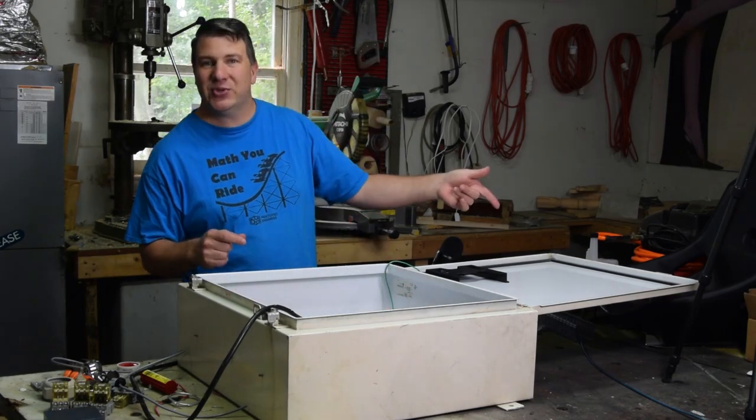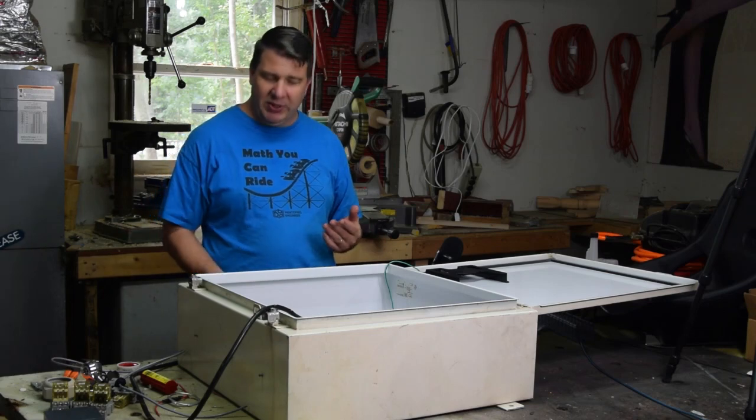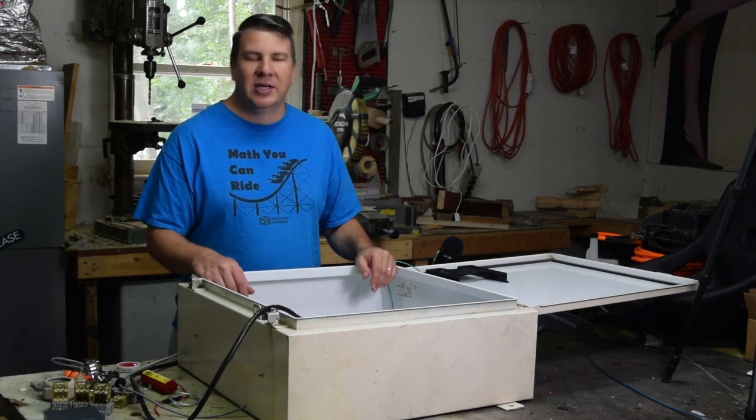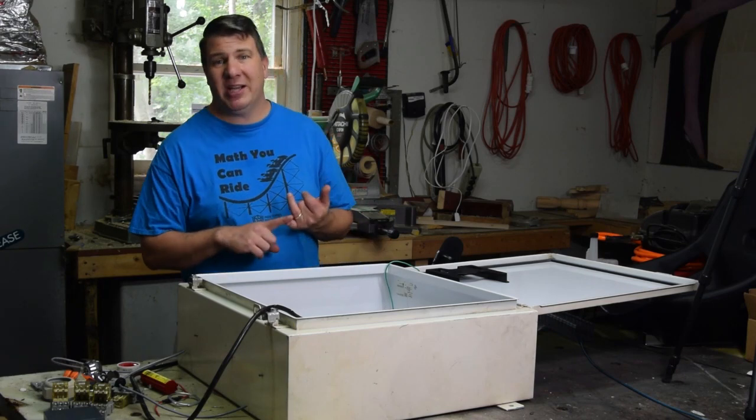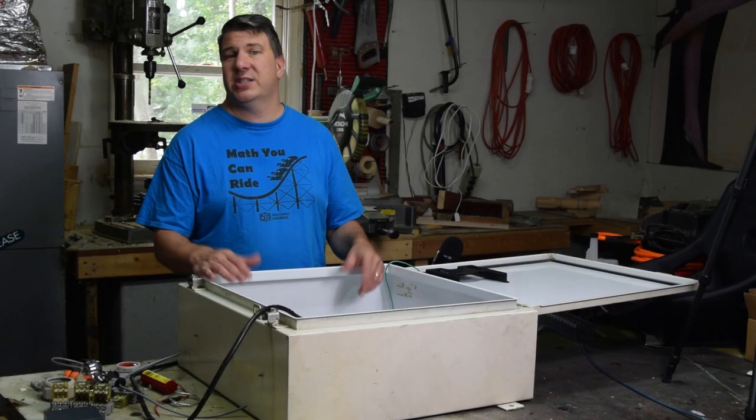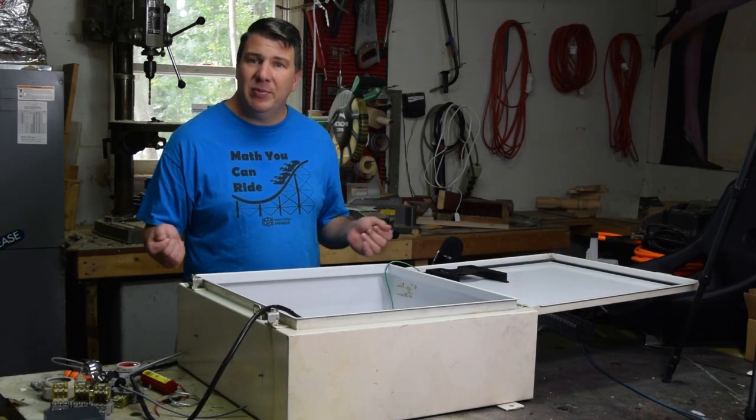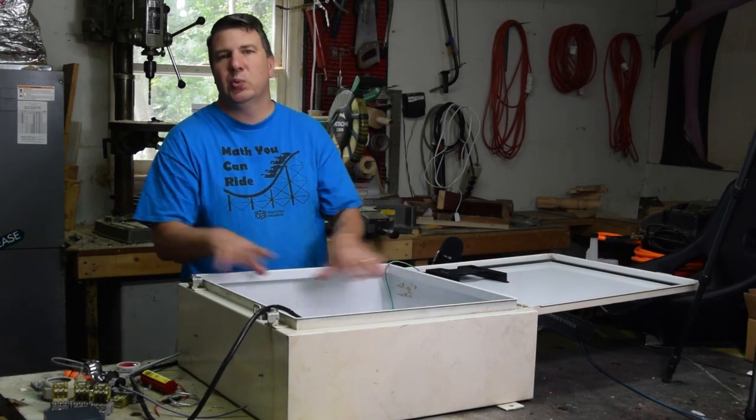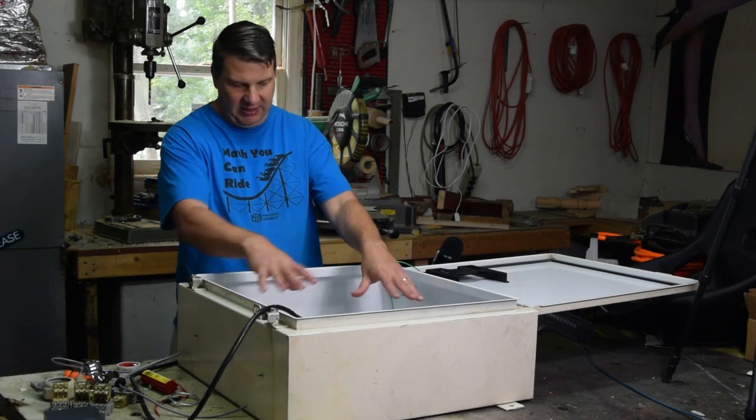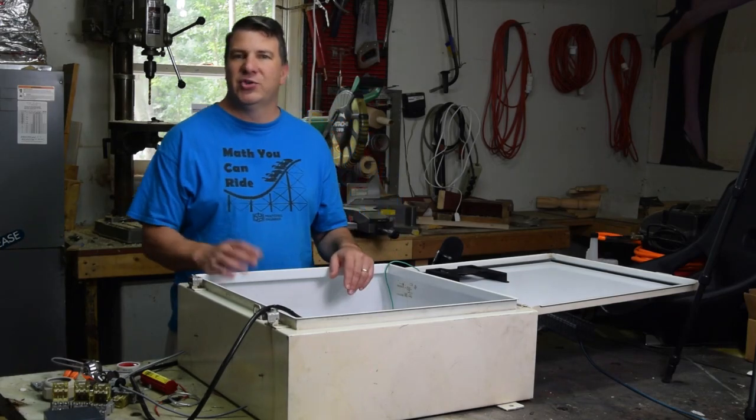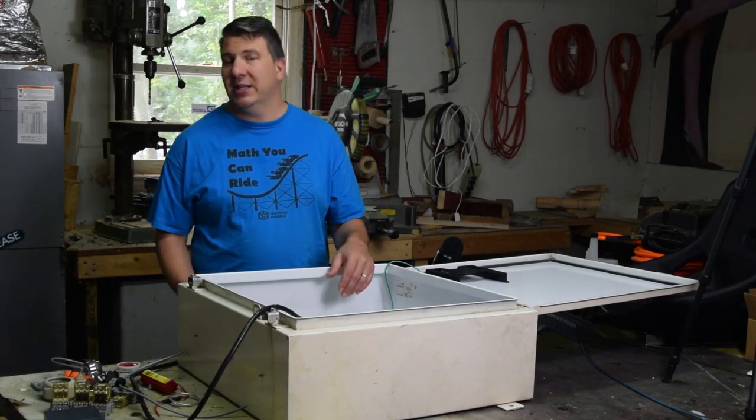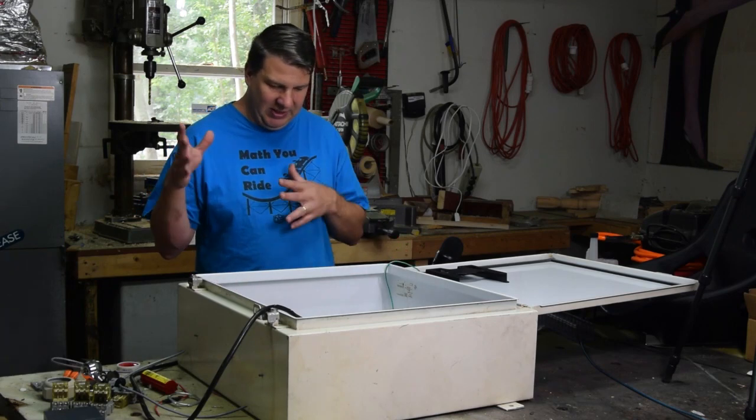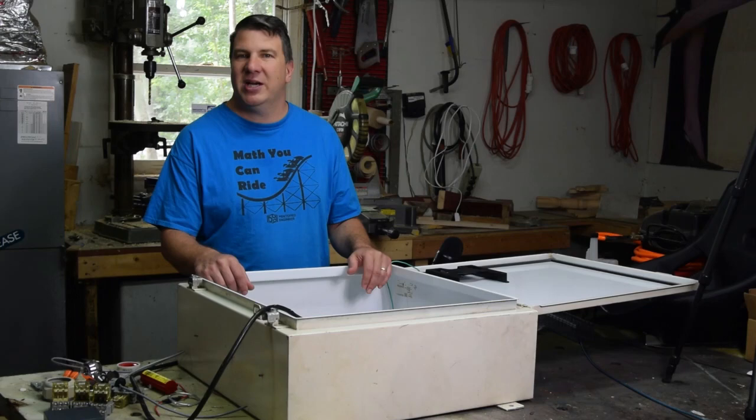Now five seconds after adding that switch right there somebody's gonna come up to you and say hey we need another sensor running in from the bottom can you drill us another hole? Of course you say no not gonna do that we don't need that sensor but you really do. So we're gonna need some supplies we're gonna need that shop vac again we're gonna need the paper towels and the Windex. In addition we're gonna need some trash bags that work great and some tape usually like the blue painters tape or something. And we're gonna tape up everything so that no shavings of any type of steel get on the equipment that's already there. Now two-man job here you're gonna be drilling in usually from the bottom up so that less shavings get in and you're gonna have somebody sucking from the top down. That will allow you to minimize the damage and then you'll go ahead and clean it up with your paper towels and Windex again.